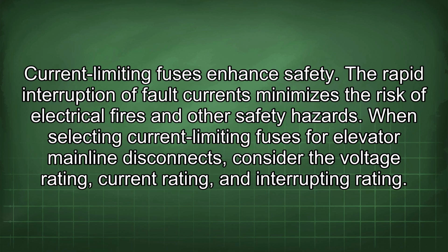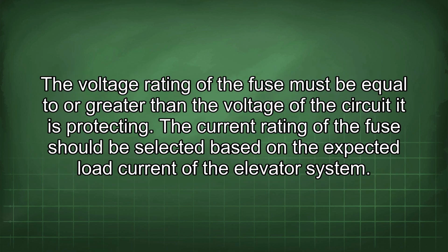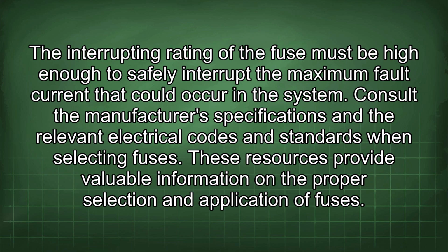When selecting current-limiting fuses for elevator mainline disconnects, consider the voltage rating, current rating, and interrupting rating. The voltage rating of the fuse must be equal to or greater than the voltage of the circuit it is protecting. The current rating of the fuse should be selected based on the expected load current of the elevator system. The interrupting rating of the fuse must be high enough to safely interrupt the maximum fault current that could occur in the system. Consult the manufacturer's specifications and the relevant electrical codes and standards when selecting fuses. These resources provide valuable information on the proper selection and application of fuses.